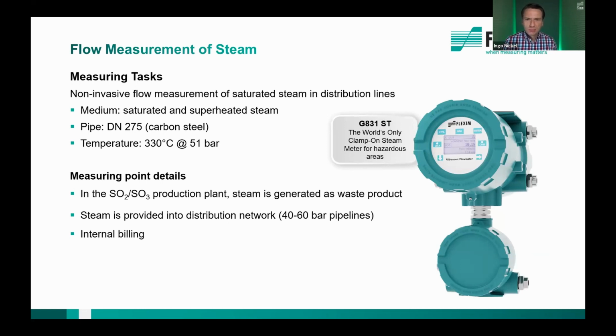Why is steam so important? Steam contains a tremendous amount of energy. It is produced from water, and steam is commonly used in the chemical process industry for process heating, power generation, but also for cleaning tasks. Measuring steam flow is very challenging and can be very cost-intensive for inline meters if the pipe size is larger than DN 150, because then the vortex flow meters are quite expensive, and also other technologies. But with a clamp-on flow meter, being able to measure the steam without opening the pipe is quite nice.